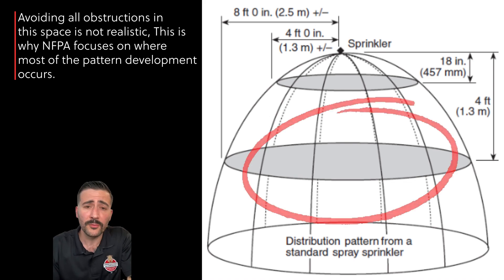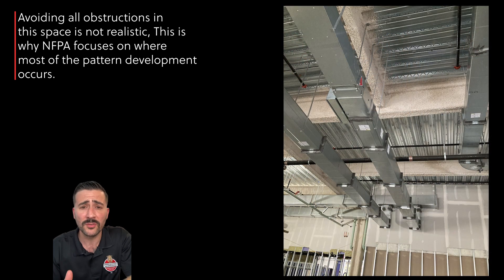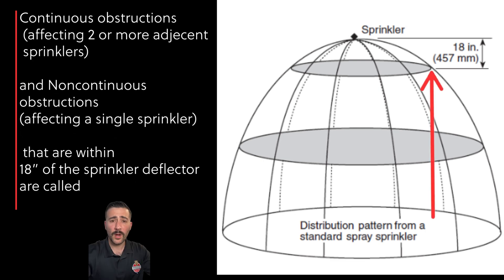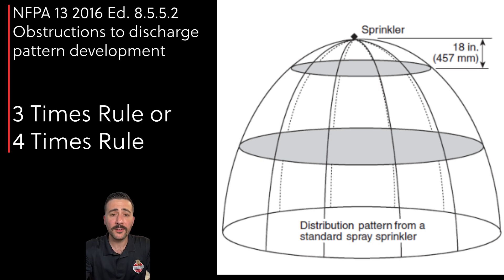If you're in the business, you know there's always going to be pipes, conduit, ductwork, and structural steel underneath our sprinkler heads. This is why NFPA focuses on where most of the pattern development occurs. Continuous obstructions affecting two or more adjacent sprinklers, and non-continuous obstructions affecting only a single sprinkler that are within 18 inches of the deflector, are called Obstructions to Discharge Pattern Development.